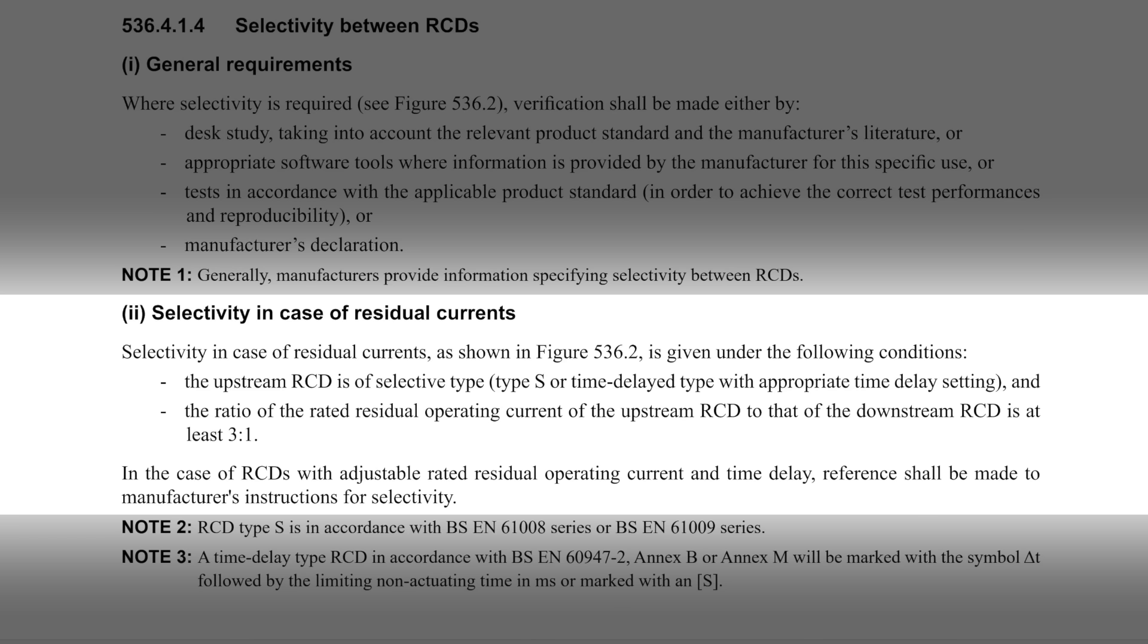And the ratio of the rated residual operating current of the upstream RCD to that of the downstream RCD is at least 3 to 1.